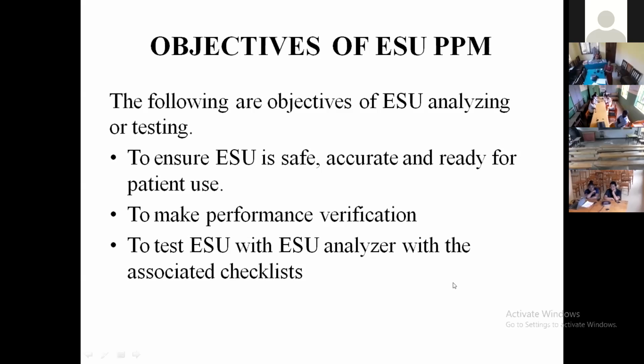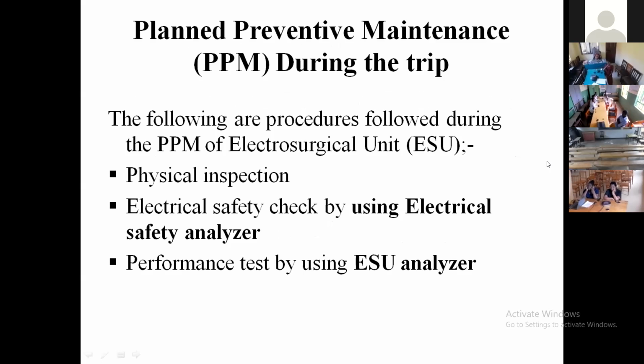Also, we make these PPMs, preventive maintenance, to do performance verification. We have to know that the equipment is performing to our qualifications, or performing under qualification. So when we make a PPM, it lets us know the performance verification. Also, you can see it tests the ESU with ESU analyzers with the associated checklists. As we can see, we have got checklists that we can notice ahead as we move on. We have checklists.